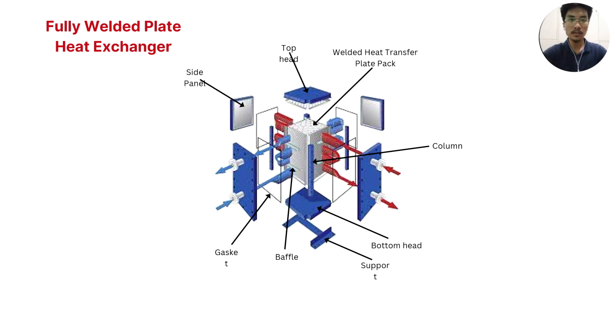This slide shows the illustration and the corresponding parts of a four-sided detachable fully welded plate heat exchanger, also known as a Compabloc. This is one of the most common welded plate heat exchangers, and as you can see, these are the basic or common parts. These include the top and bottom head, four side panels, welded heat transfer plate pack, column baffle, gasket, and support.